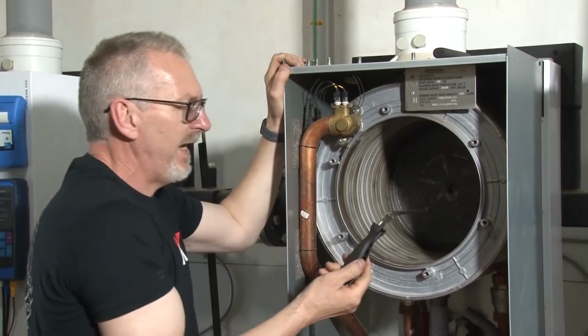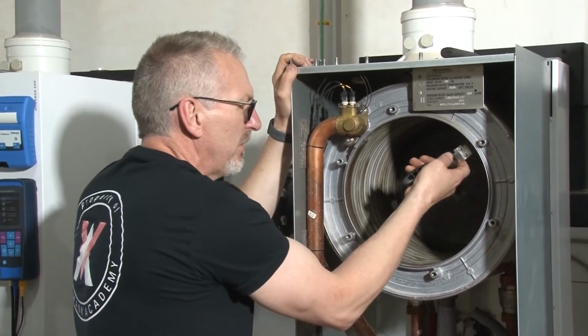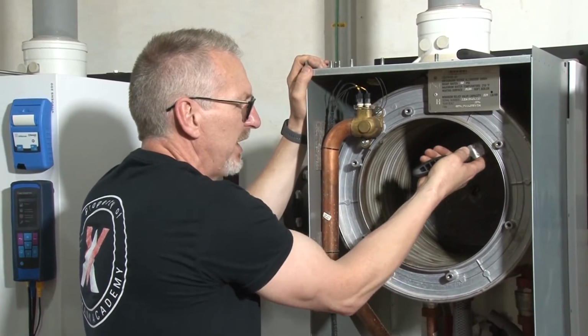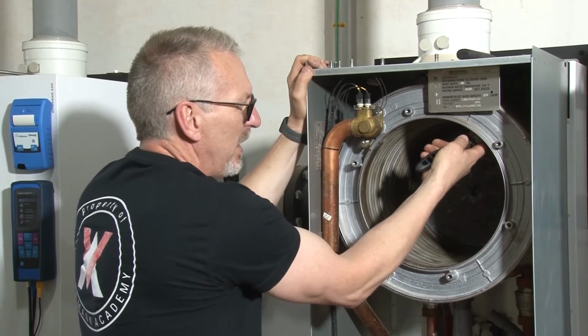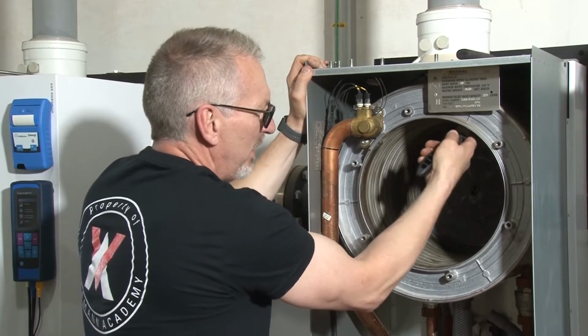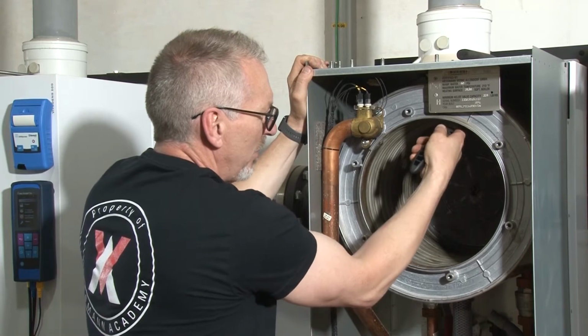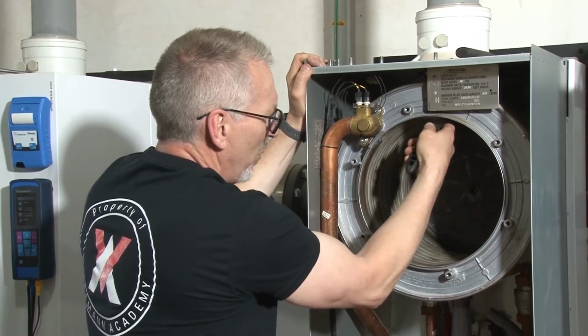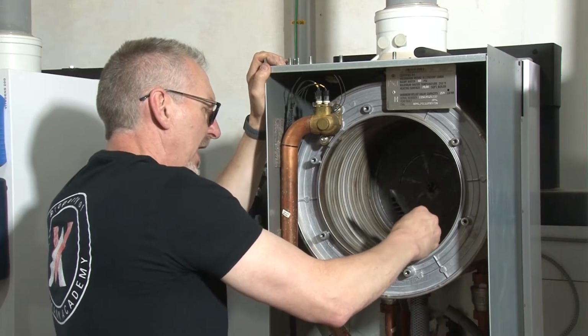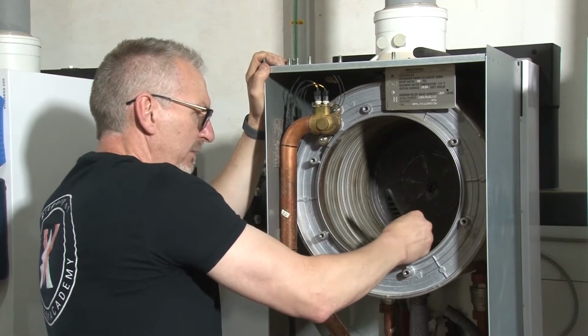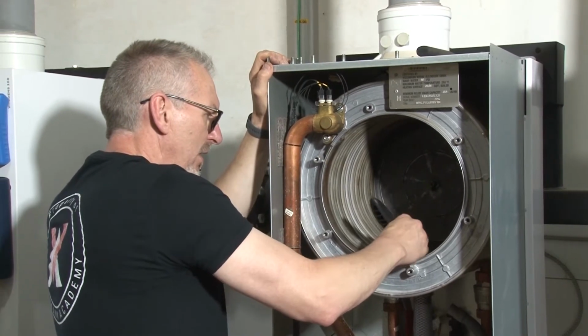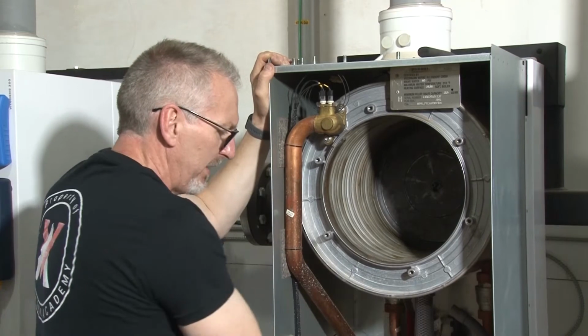If you're dealing with a lot of F1 faults, I would also encourage you, because you might have some really contaminated combustion air, for instance, you want to go up in the top areas here as well, and just check to make sure that we have these nice and open as well. If I found a spot in here that I couldn't get that knife through, for instance, there's areas in here, what I could do at that point in time is take some chemical.